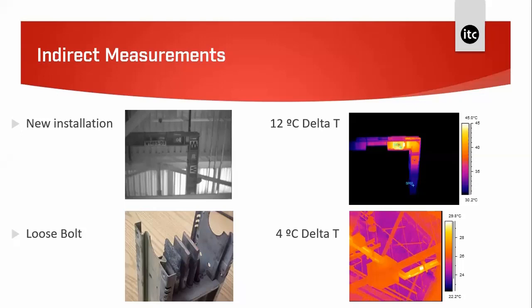Added to this problem is the fact that many busbars have a low emissivity finish on the exterior — meaning they could be reflective. Some knowledge of the construction and assembly can help give an indication of where the joints are. Local heating near a joint could indicate a problem with the joint, and the temperature inside may be really high even when the external temperature rise appears low.